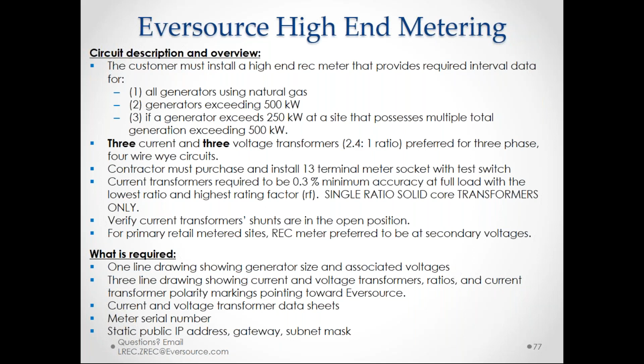What is required: the line diagram has to clearly show the generator size and voltages, clearly show the ratios on the CTs and VTs and their polarity markings, and you need to provide accurate data sheets with the models clearly circled.